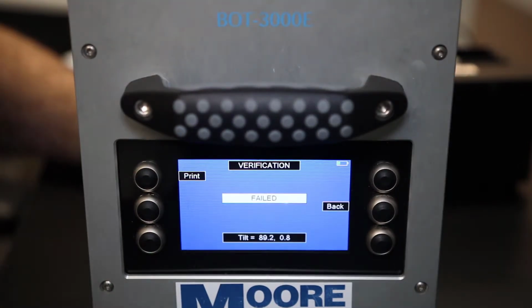However, if your BOT fails, repeat this process, placing the BOT on a flat level surface and being careful to mitigate movement in and around the area, such as walking, and make sure there is no airflow through the area. If the test will not pass after multiple attempts, there may be an issue with the machine and you should contact the manufacturer.